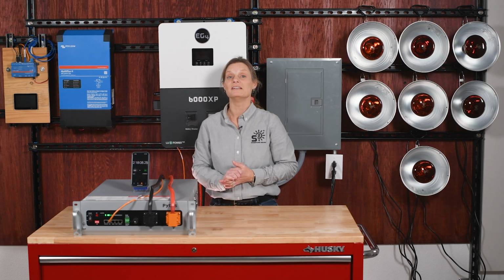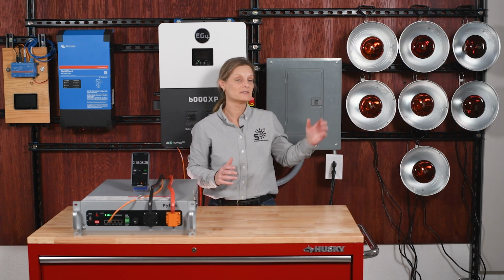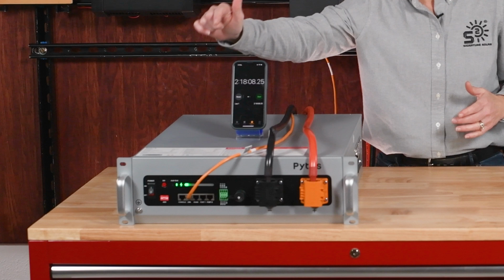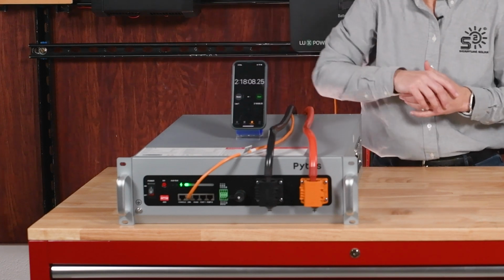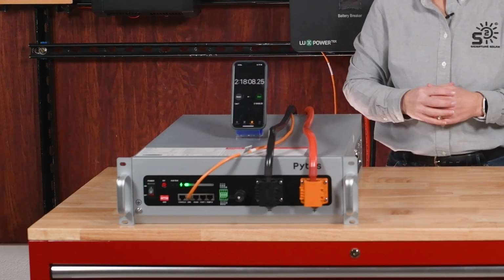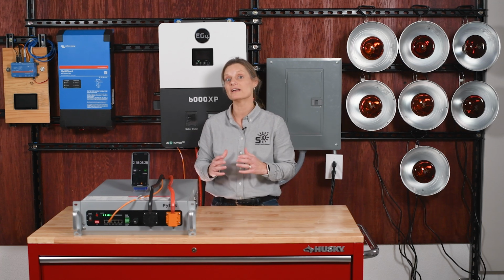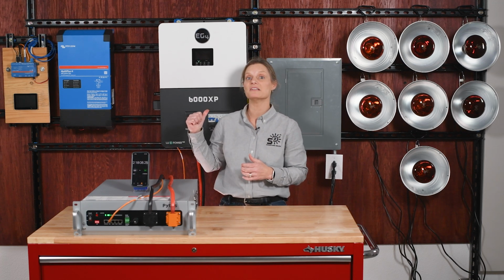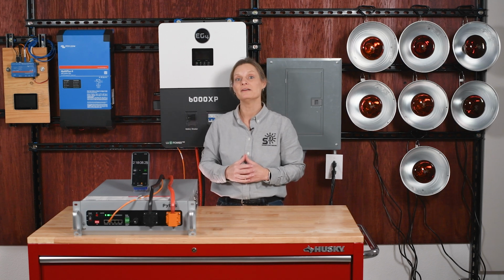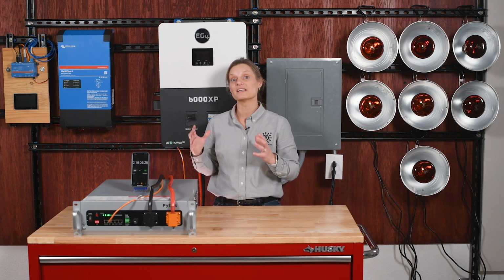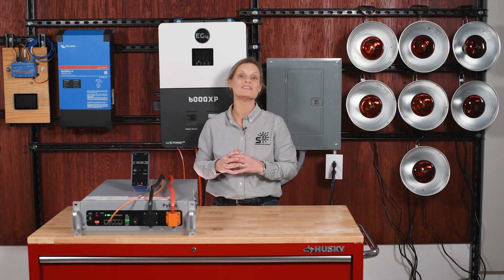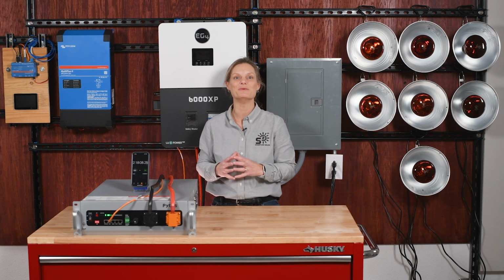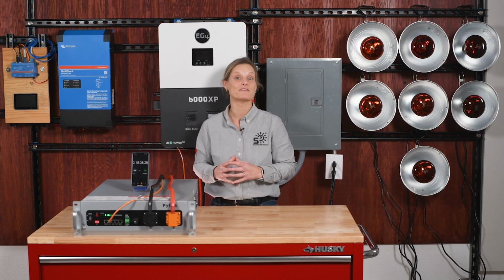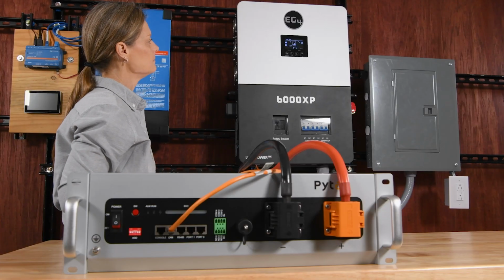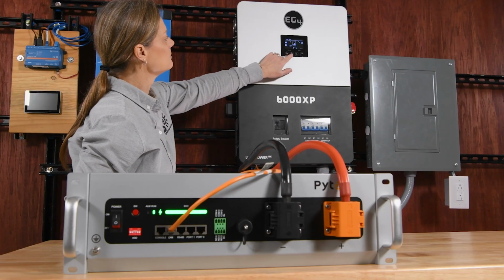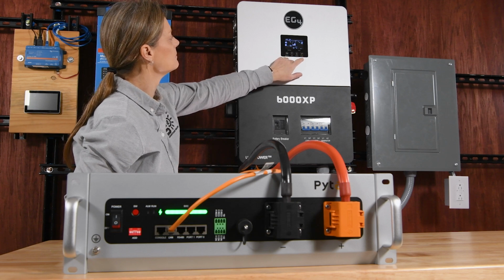So we have finally completed our discharge test. Our lights went off, our inverter went off, and notice there's still a slight bit of state of charge on our battery display there. I need to make a slight correction in our calculations based on the UPS settings displayed on the screen. While running these loads, the inverter was actually outputting approximately 1.73 kilowatts as indicated by the UPS reading, which I did not notice at first. However, the battery itself was delivering 1.84 kilowatts, which must have been accounting for efficiency losses in the system.